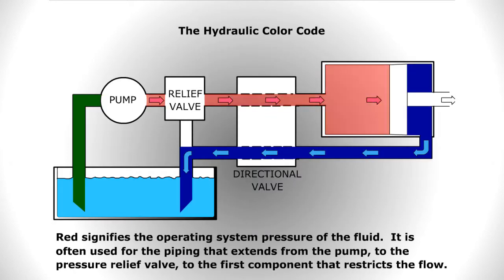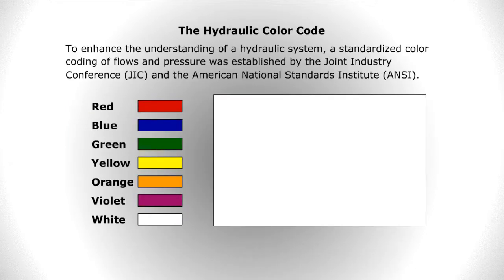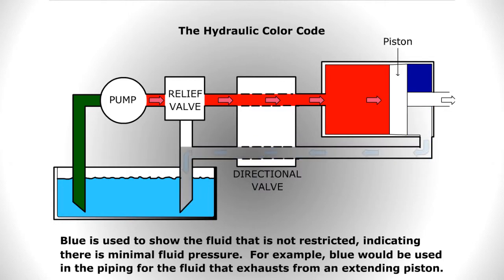Red signifies the operating system pressure of the fluid. It is often used for the piping that extends from the pump to the pressure relief valve to the first component that restricts the flow. Blue is used to show the fluid that is not restricted, indicating there is minimal fluid pressure.